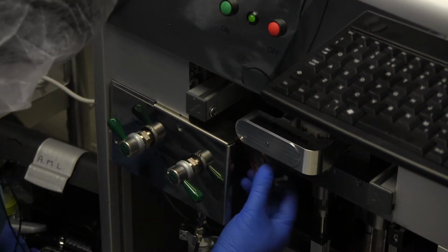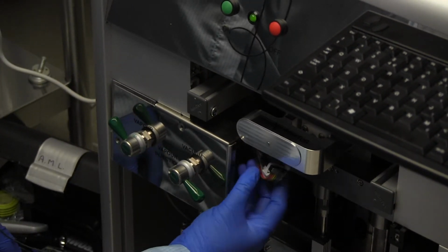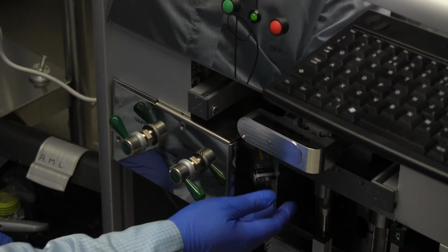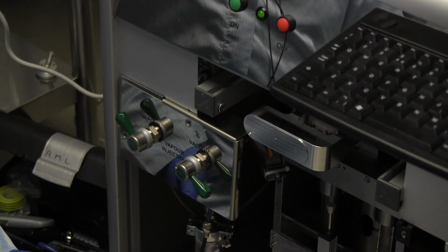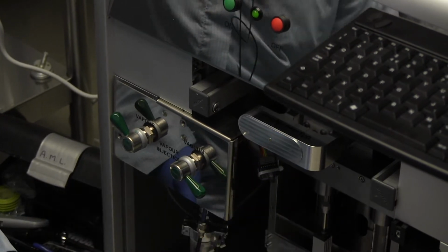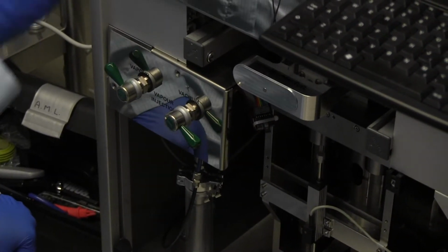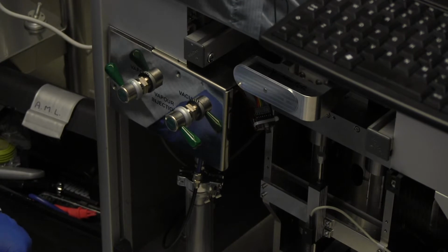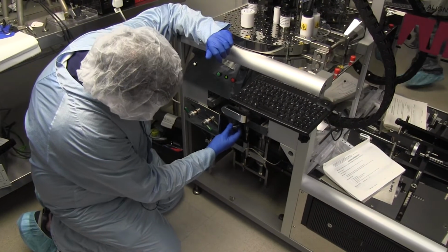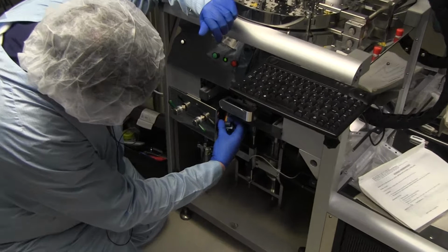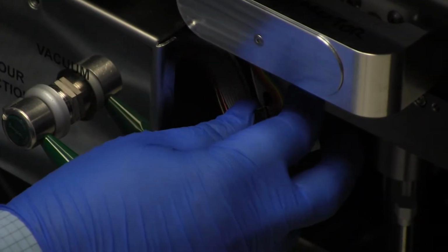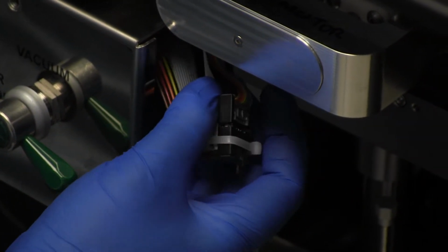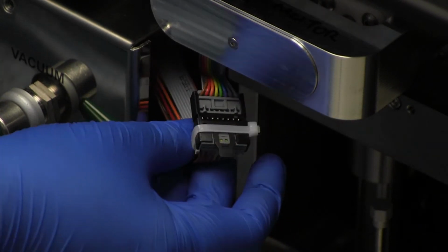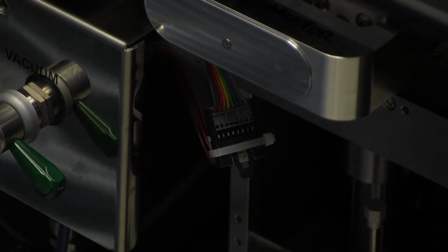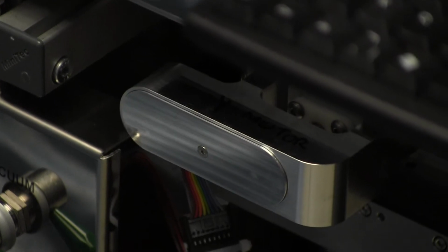Another problem that might happen is if there's some break in the wiring - if it degrades, or you cut it by mistake - you'll see an error code because it can't communicate fully with the motor. There are two cables: a coloured ribbon cable that delivers power and position control, and a grey ribbon cable for the encoder. That's how the motor controllers know and monitor the position of the motor.